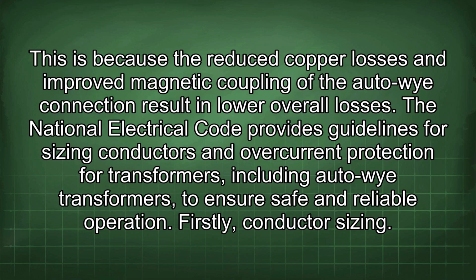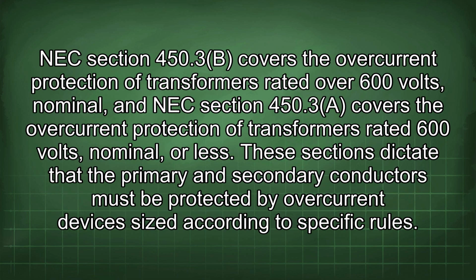The National Electrical Code provides guidelines for sizing conductors and overcurrent protection for transformers, including Auto-Wye transformers, to ensure safe and reliable operation. Firstly, conductor sizing. NEC Section 450.3(B) covers the overcurrent protection of transformers rated over 600 volts, nominal, and NEC Section 450.3(A) covers the overcurrent protection of transformers rated 600 volts, nominal or less.